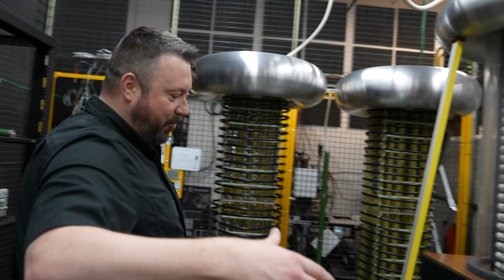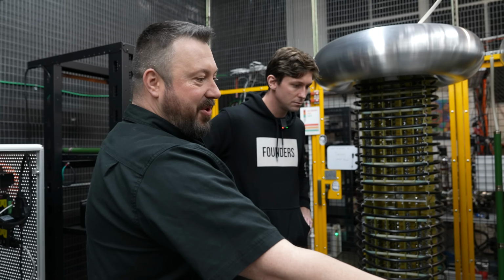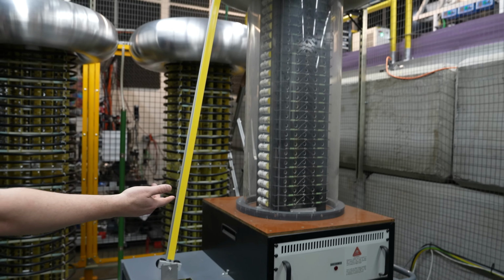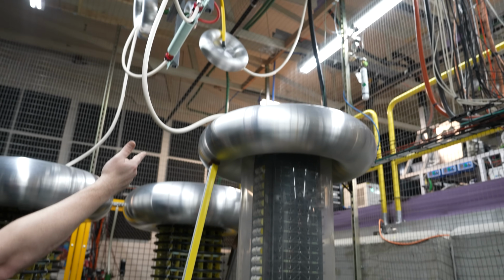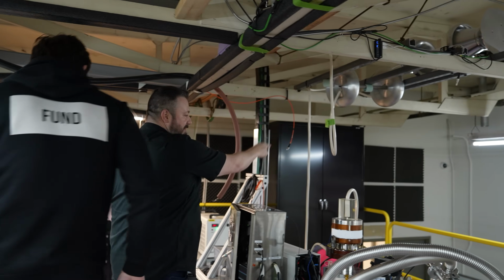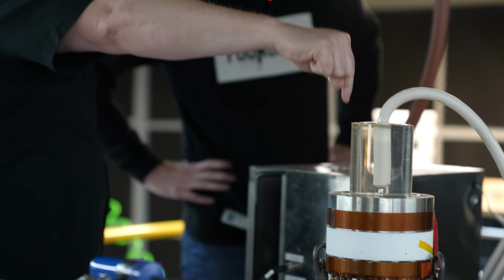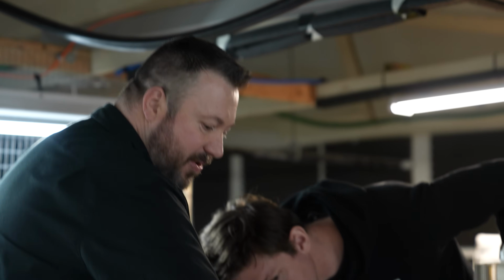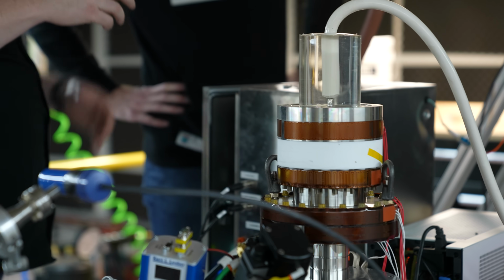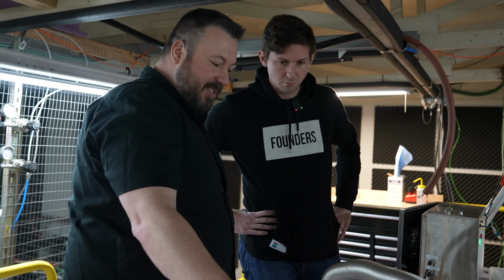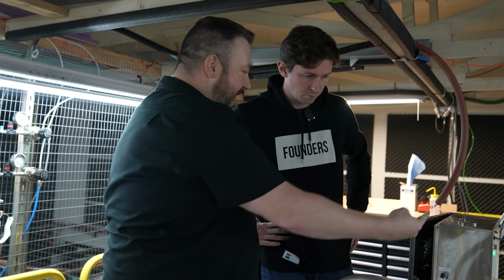These are our high voltage power sources. This takes wall plug power, 120 volts AC, rectifies it up the ladder, comes up over the ceiling, and then drops all the way down. High voltage comes in and energizes that cathode inside, which makes 2 milliamps of beam current, then extracts that plasma and accelerates it down the beam line.